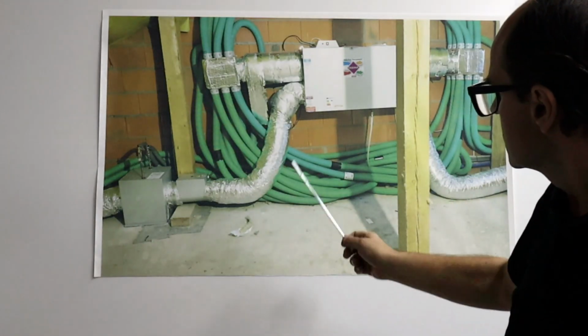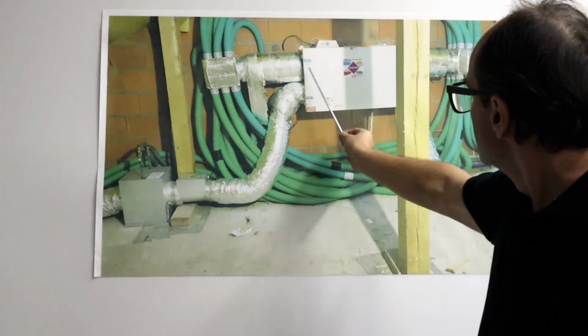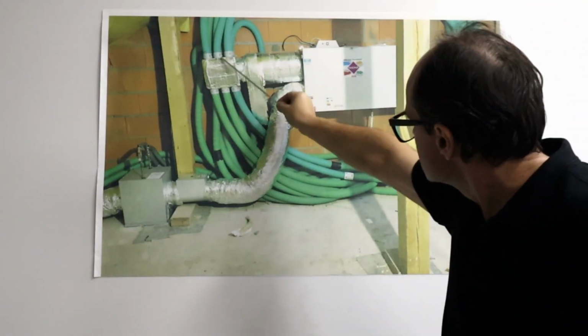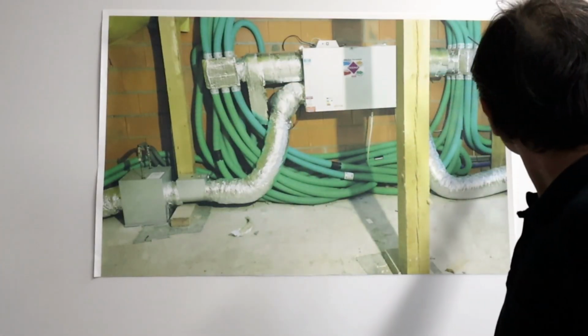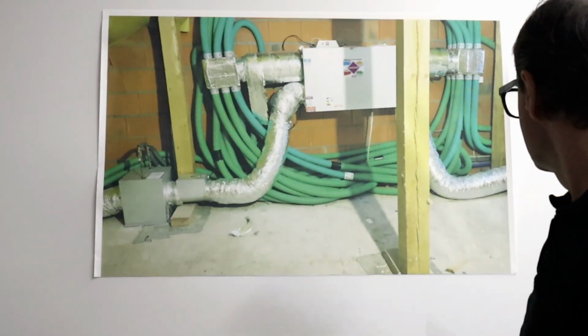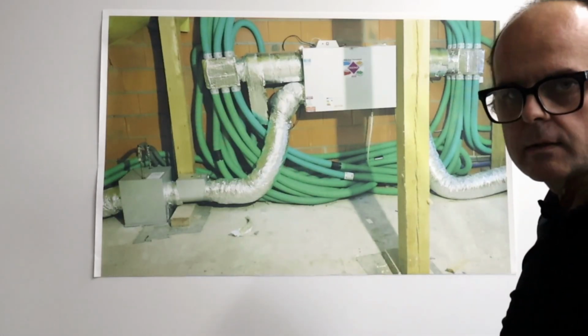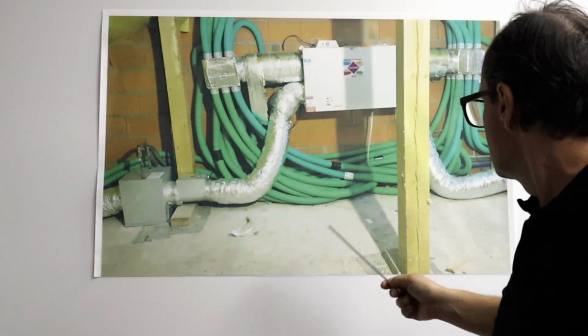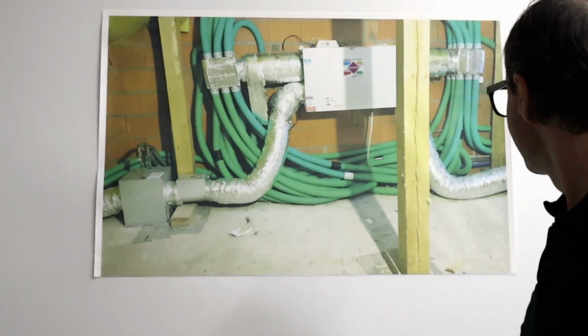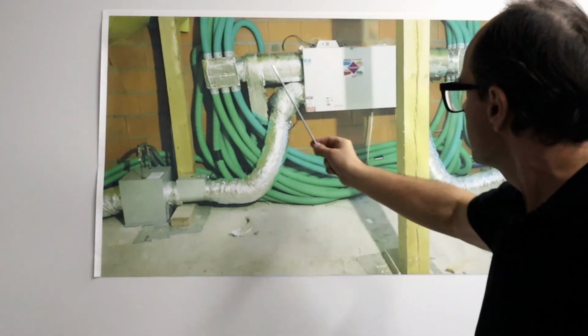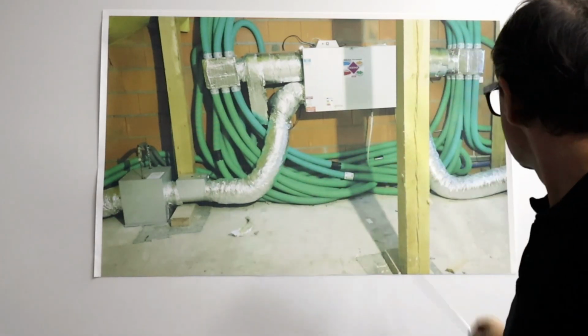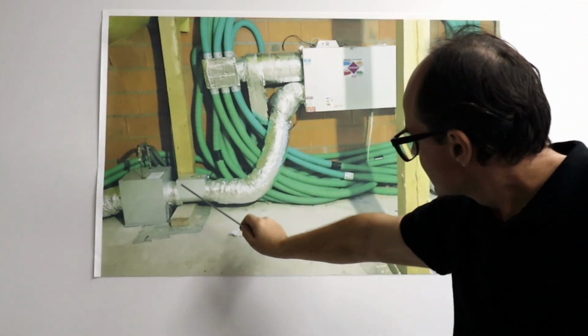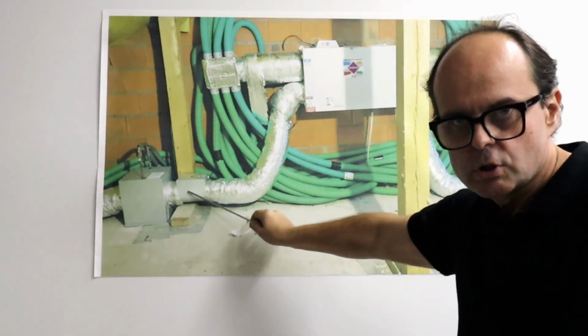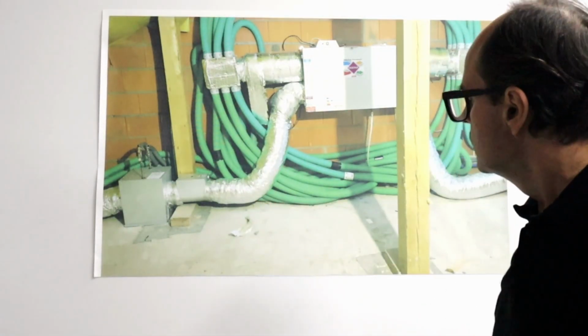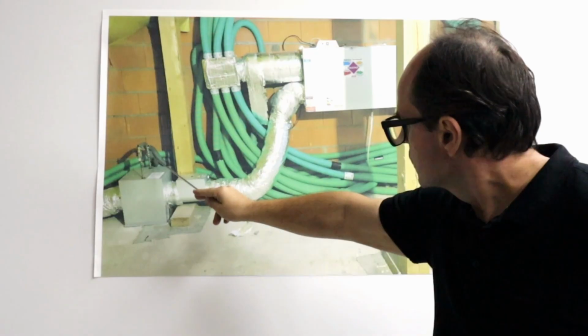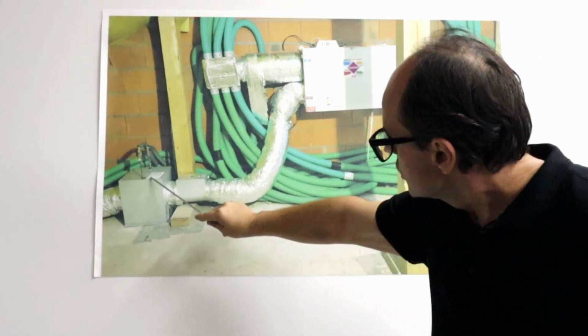It will be impossible to clean this system. It has no value at all. Any heat we recover, we lose with this setup because nothing is insulated. This isn't done in an insulated attic. There will be nothing but energy loss here. Water from the diffusers will condense. There's no air tightness here. Air won't even reach the rooms. This heater will always run at maximum power just to make it a little bit warmer. Of course, there's no glycol heat exchanger here. It's connected directly to the water buffer tank, so in winter it will freeze.